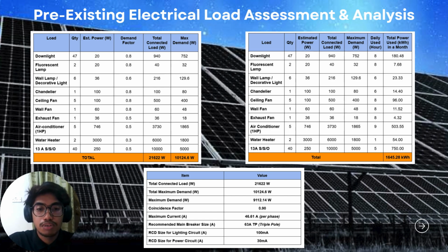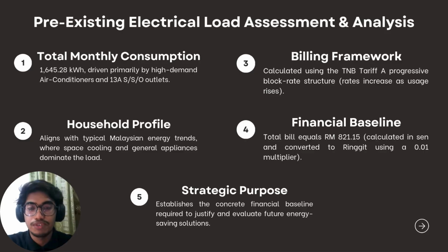The size of RCD we get is 63 ampere, 30 milliampere for the power circuit, and 100 milliampere for the lighting circuit. Alright, for further explanation I divide it into 5 parts. The first part is the total monthly consumption for the pre-existing electrical load assessment and analysis, 1,645.28 kilowatt hour, driven primarily by the high demand air conditioners and 13A SSO outlets.